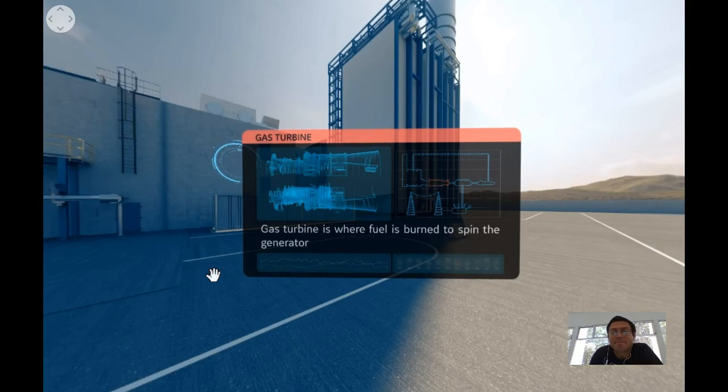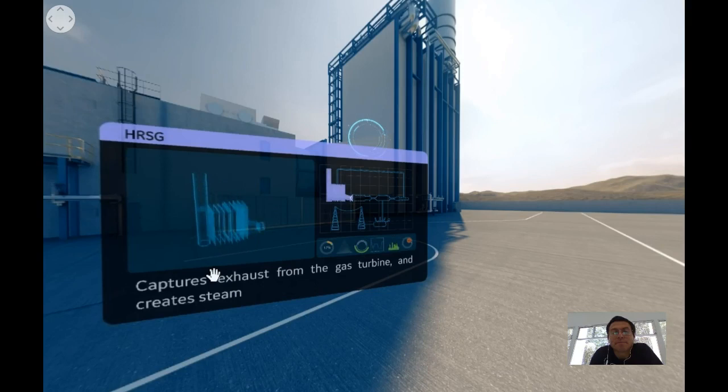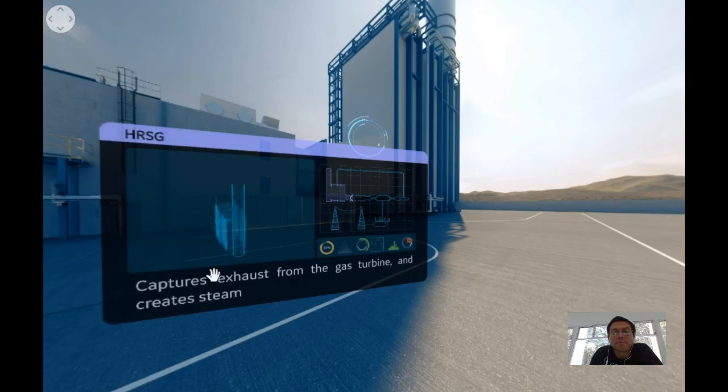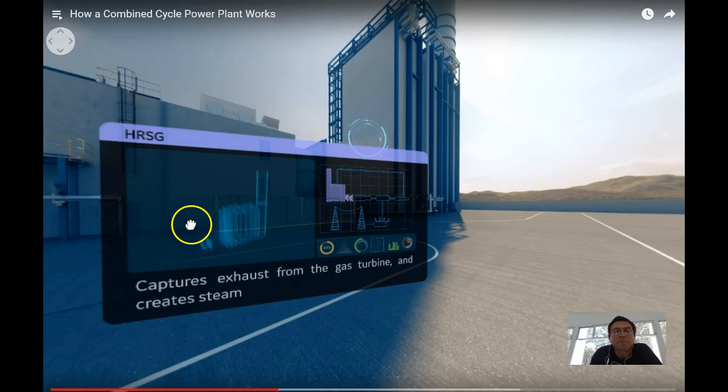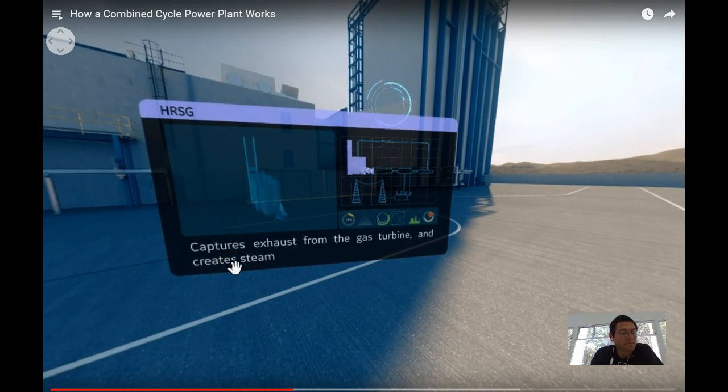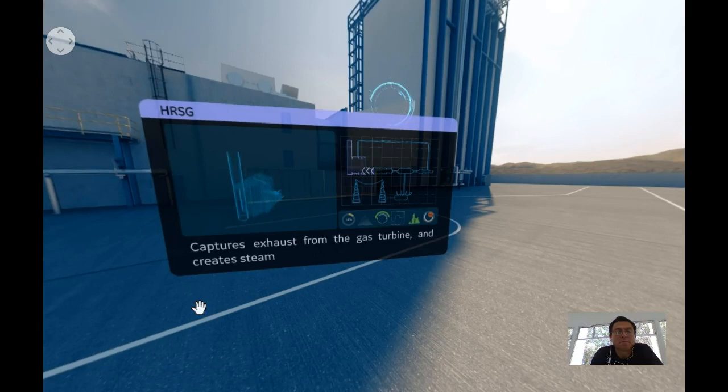Behind the gas turbine you can see another key component, the heat recovery steam generator, HRSG. Its mission is to capture exhaust heat from the gas turbine that would otherwise escape through the exhaust stack. Thanks to the captured exhaust heat, the HRSG generates steam where it is then delivered to a steam turbine, making even more electricity.